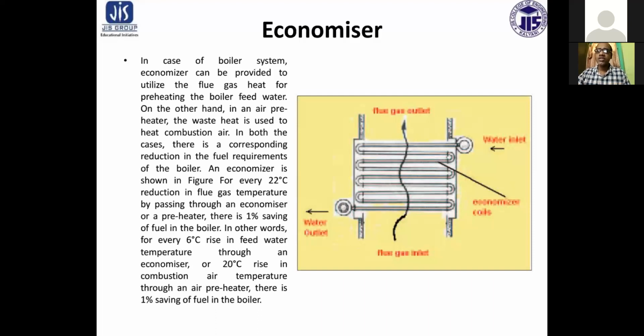In the boiler, where the fuel is burning, the flue gas leaving the boiler can be at a temperature as high as 1200 degrees centigrade. If we leave that flue gas to go out through the chimney, it will be an ultimate loss of energy. So in the path of the flue gas, the economizer, air preheater and some other auxiliaries are placed.